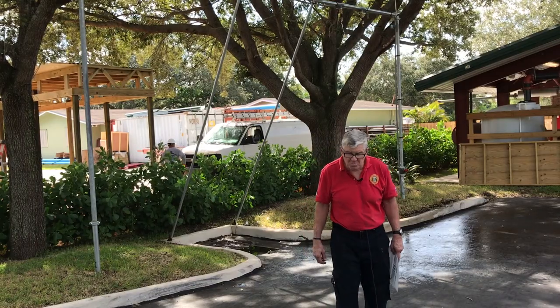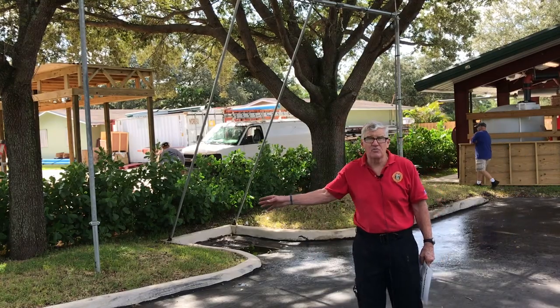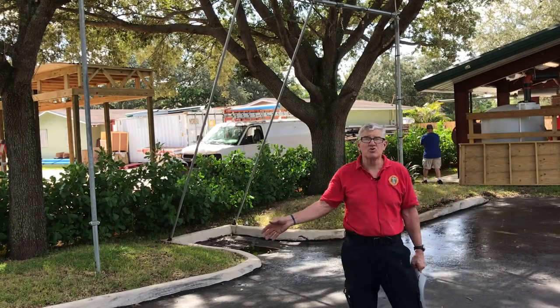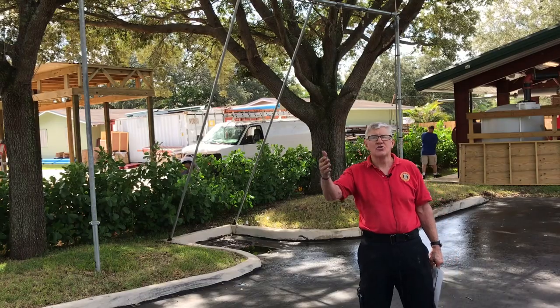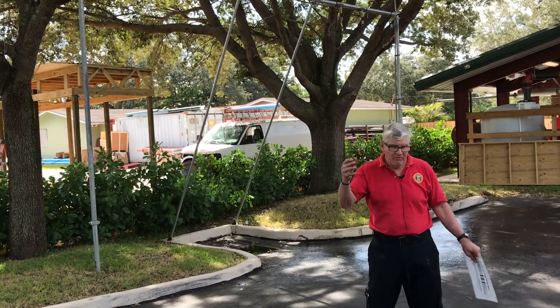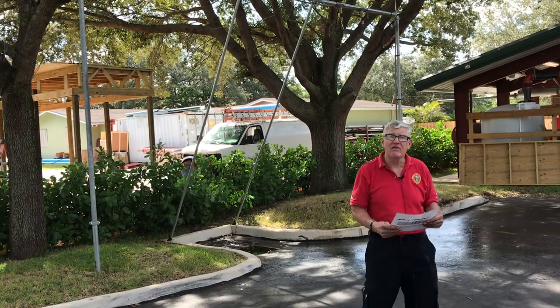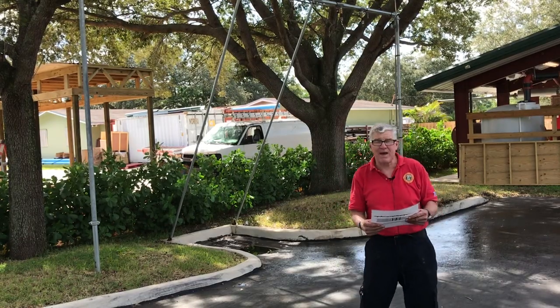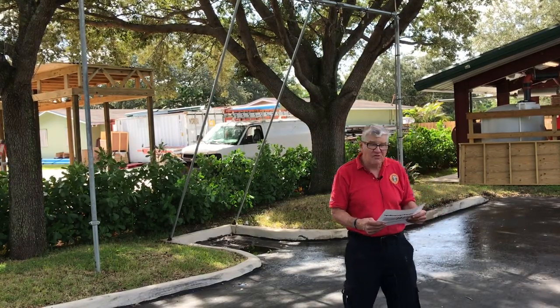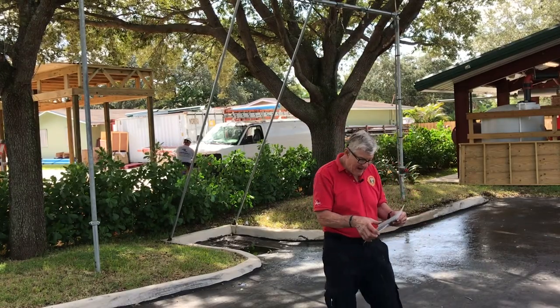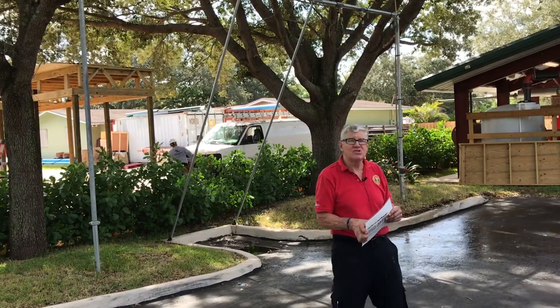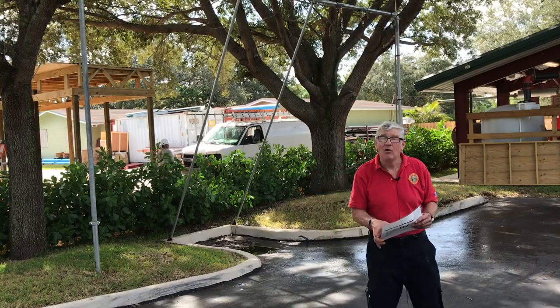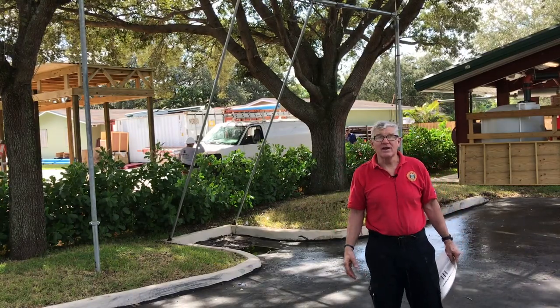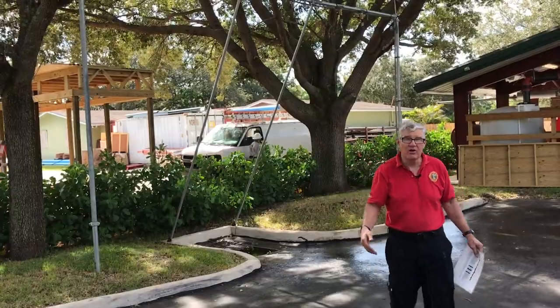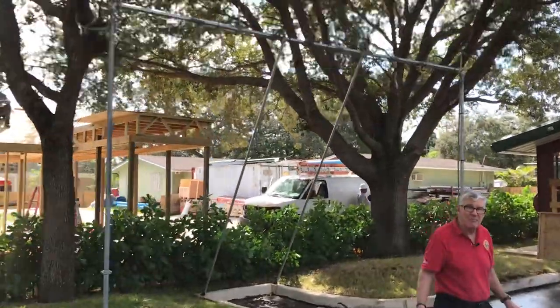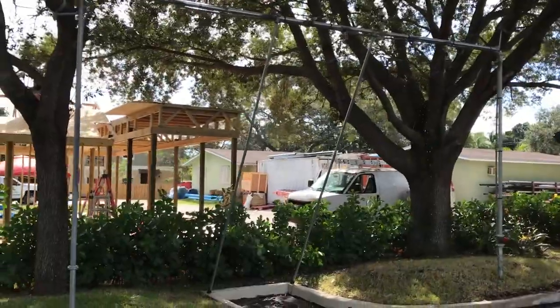All right, this is the array of sprinkler heads at Sprinklermatic. From the left, we have residential heads, such as what you'd see in an apartment for a 13R, 13D sprinkler system. Very low flow. The first head is a Viking sprinkler head. It is a pendant head. It is designed to flow 26 gallons per minute at 21.6 PSI. Now, we're going to get wet, AJ, so we're going to have to move the camera over here just a little bit, and we'll focus up on the head. It will be the one on the extreme left.